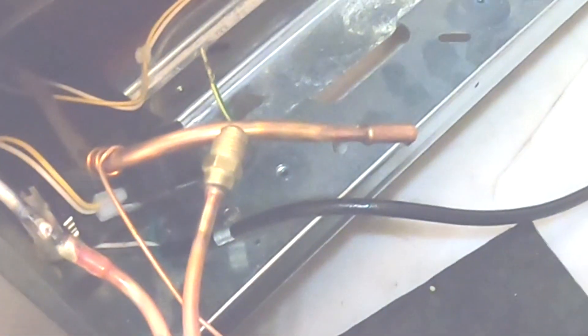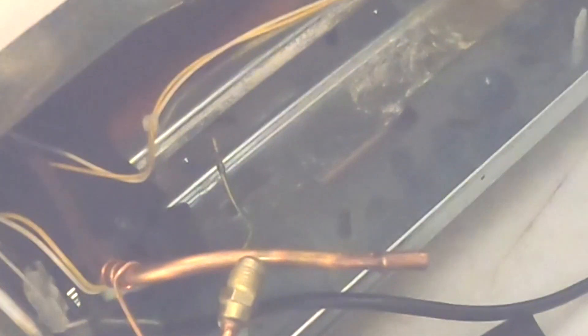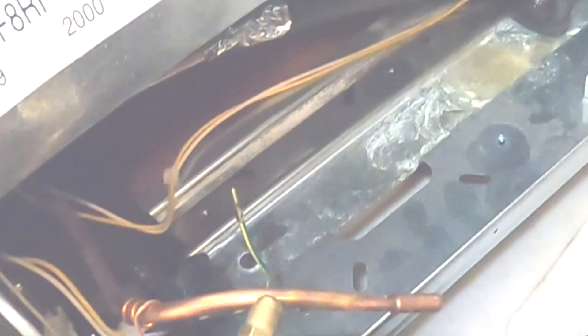It's been sucking through. All right, so there you go - that's how I know I got a blockage. It's actually oil too, there's oil in there. So that's how I know I got a bad evaporator.